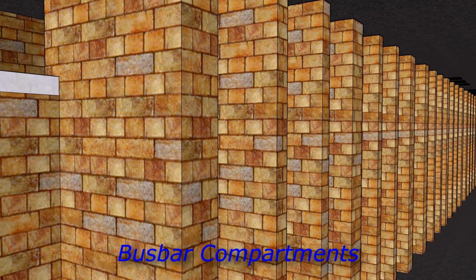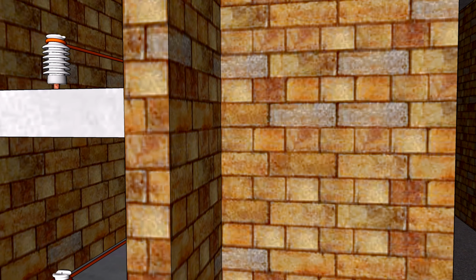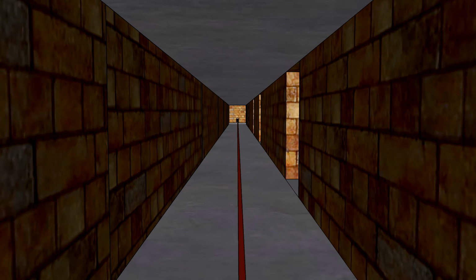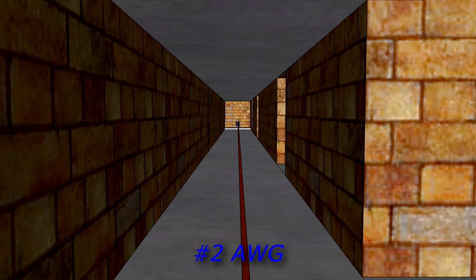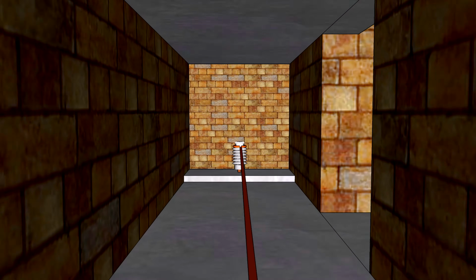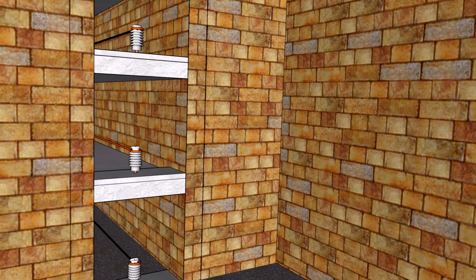The 3 high-voltage wires that came down from the wire tower through ceramic pipes entered the basement through an opening in the flue. Each of the 3 wires was then terminated on one of the 3 bus bars, each bus bar being contained within one of the 3 levels within the brick structure, and stretching almost the entire length of the building. The bus bar itself was bare number 2 copper wire, a little more than 1/4 of an inch thick, or almost 7 millimeters. From this bus bar, then, connections could be made along the length of the bus bar corridor to the various devices and machines within the building, or to external outputs, such as forwarding the high-voltage AC to other railways.